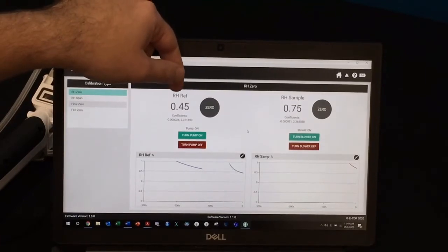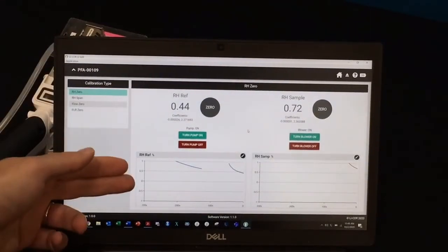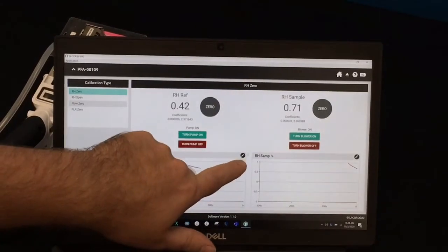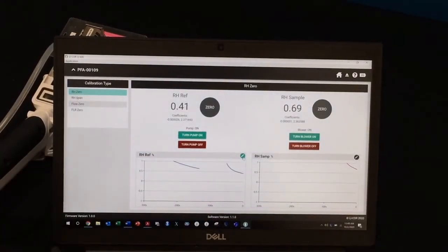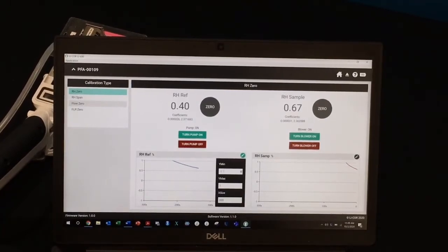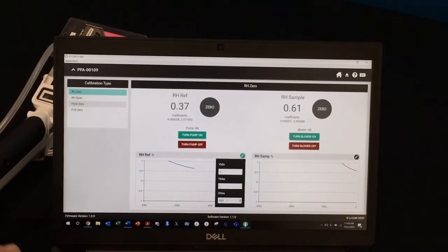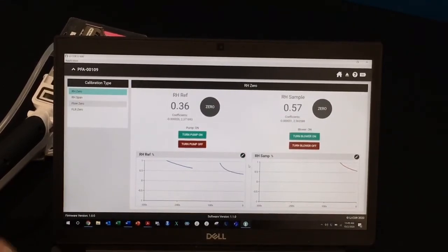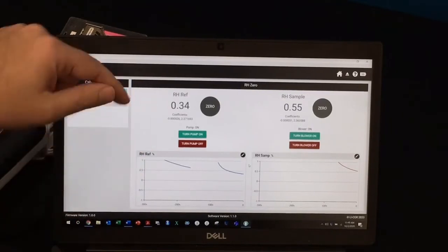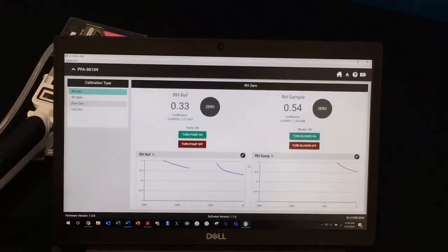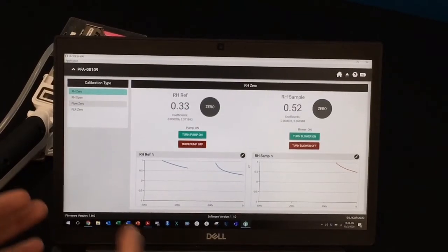This is showing the relative humidity readings for reference and sample, as well as graphs that you can edit by pressing the pencil icon in the top right corner. You can edit them so that you can see the minimum and maximum relative humidities. I usually set that to -1 as a minimum and +1 as a maximum, with a large time span, the X size value. 300 seconds should be adequate. Essentially, now that we have the instrument running, we're looking at the graph to make sure that the relative humidities drop sufficiently close to 0 and are also stable.